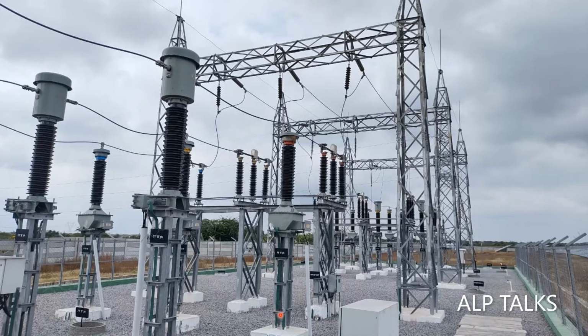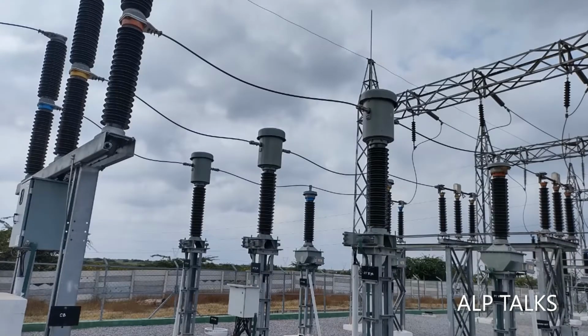Fencing, and small stones at the bottom to avoid grass growing. Many earth pits will be there, individual earth pits, and finally all earth pits will be earthed to the substation main earth grid system. Color coding will be there, RYB: red, yellow, blue, for better identification purposes. This is another view of how the system looks. We can see here how they are connected.